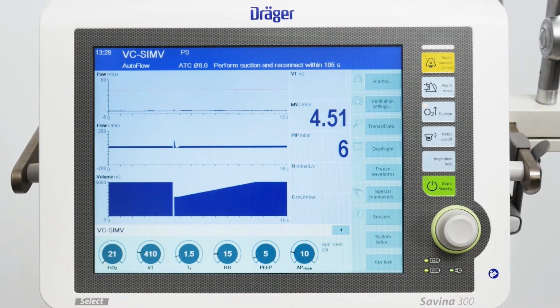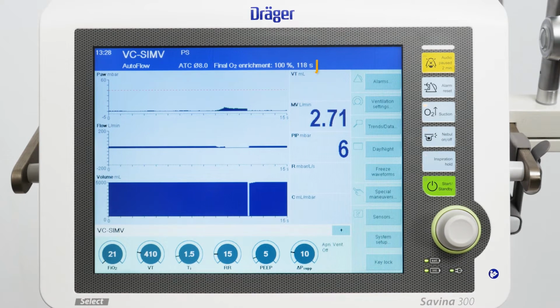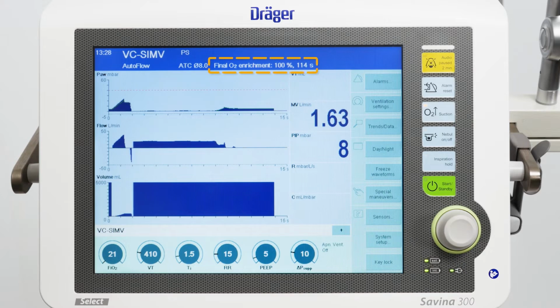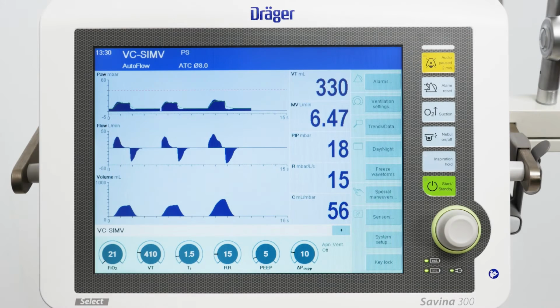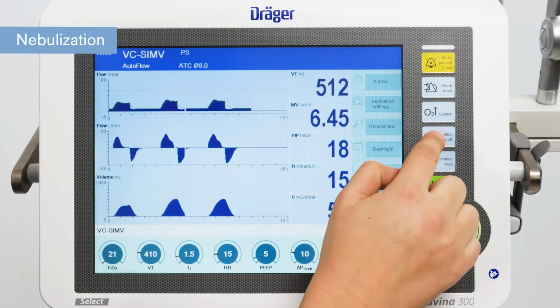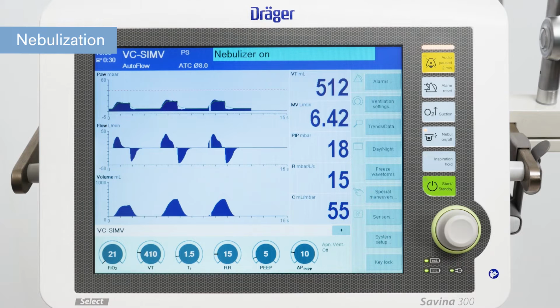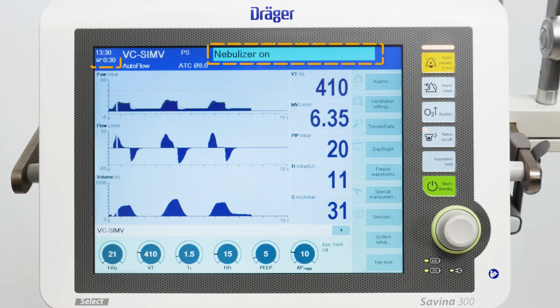Afterwards, reconnect the patient. Savina Select continues ventilating in the set ventilation mode, except that for 120 seconds, 100% volume O2 is delivered for final oxygen enrichment. Press the nebulization on-off key and Savina 300 Select starts nebulization. The nebulization time is 30 minutes. The symbol and the remaining time are displayed in the header bar.